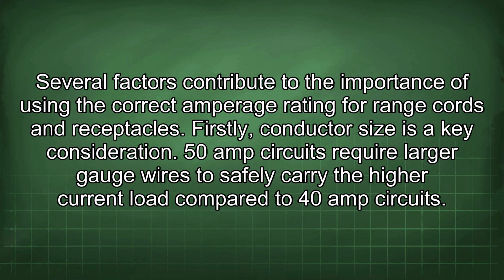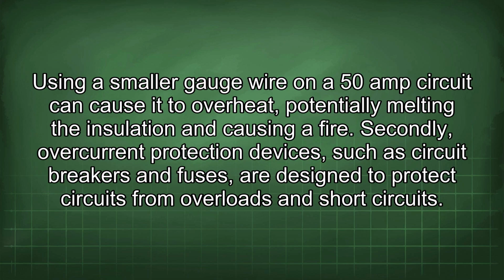Firstly, conductor size is a key consideration. 50 amp circuits require larger gauge wires to safely carry the high current load compared to 40 amp circuits. Using a smaller gauge wire on a 50 amp circuit can cause it to overheat, potentially melting the insulation and causing a fire.